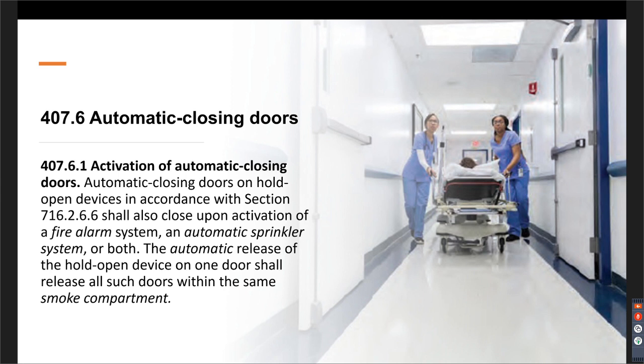There, and then the automatic release of this last sentence is new. The automatic release of the hold-open device on one door shall release all such doors within that same smoke compartment. Not new in practice, it's just now spelled out in the code that if that one door that's on a hold-open is released, then all similar doors have to also release.